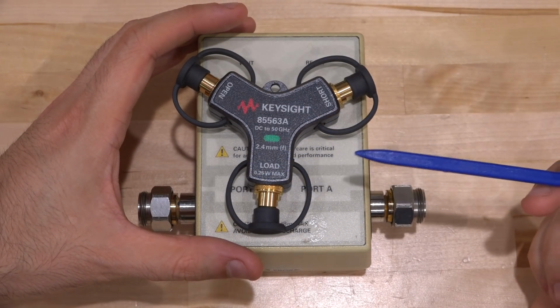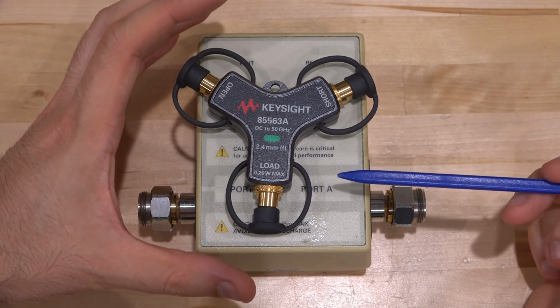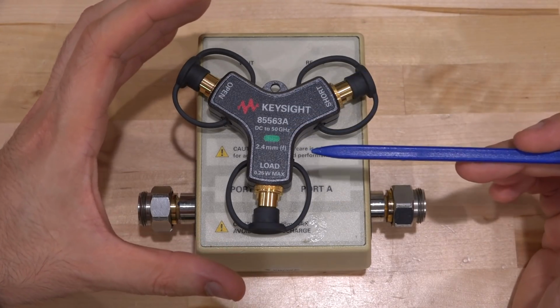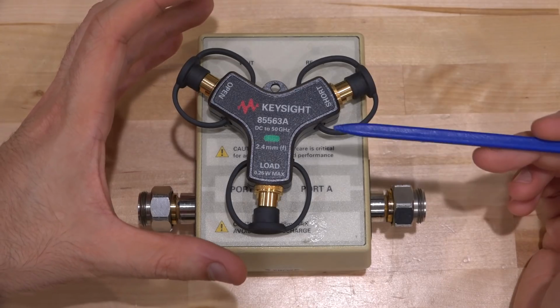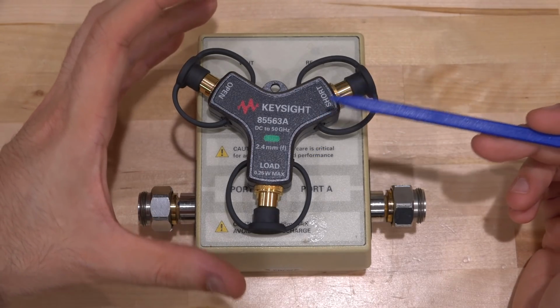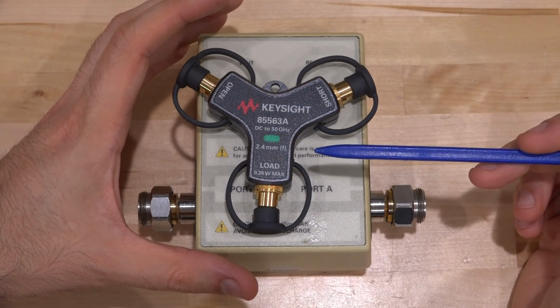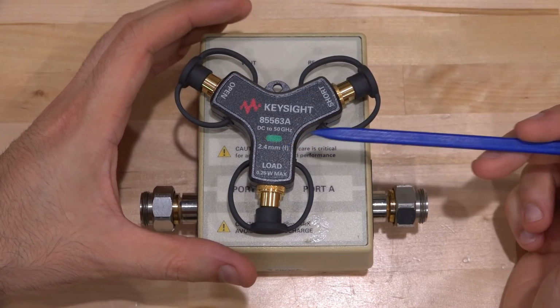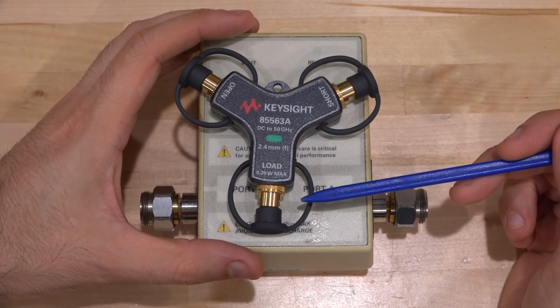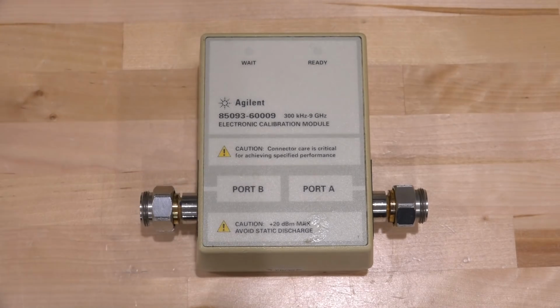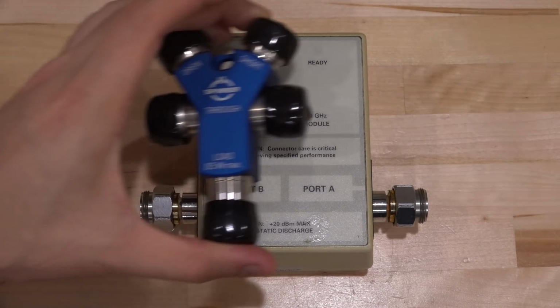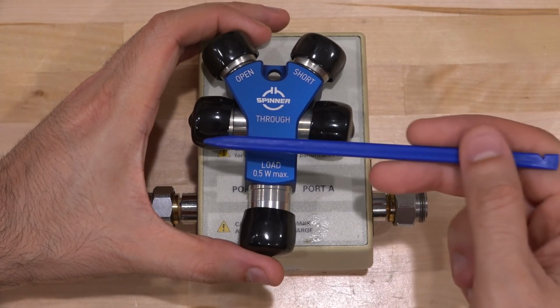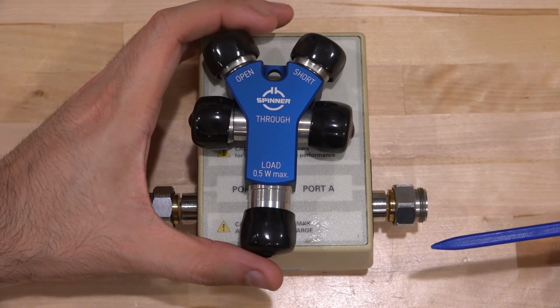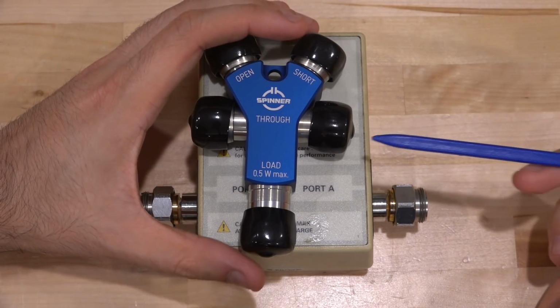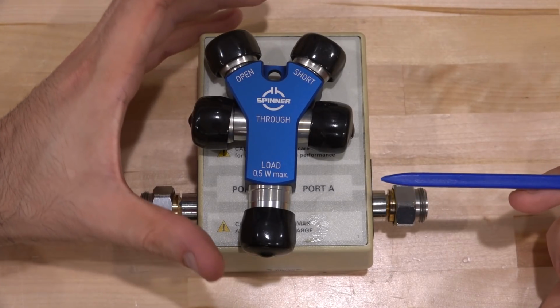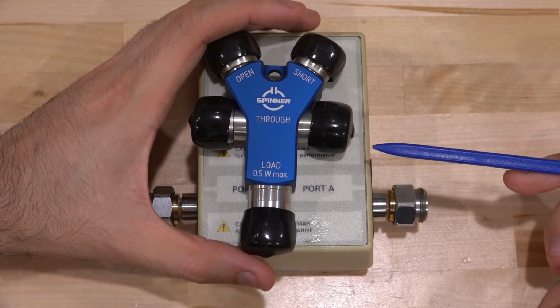So every one of these calibration kits is going to have some imperfections associated with it, and sometimes they come with a disk that tells you what those imperfections are. What is the additional capacitance or inductance or so on these different ports. So when the instrument measures these, it takes those into account when it does the final calibration. So here's another example, one that's type N. This one has a through on it as well, so it is all nicely connected to each other. You can get these, of course, separate, but having them all connected to each other kind of makes sure you don't lose them. It's very convenient.